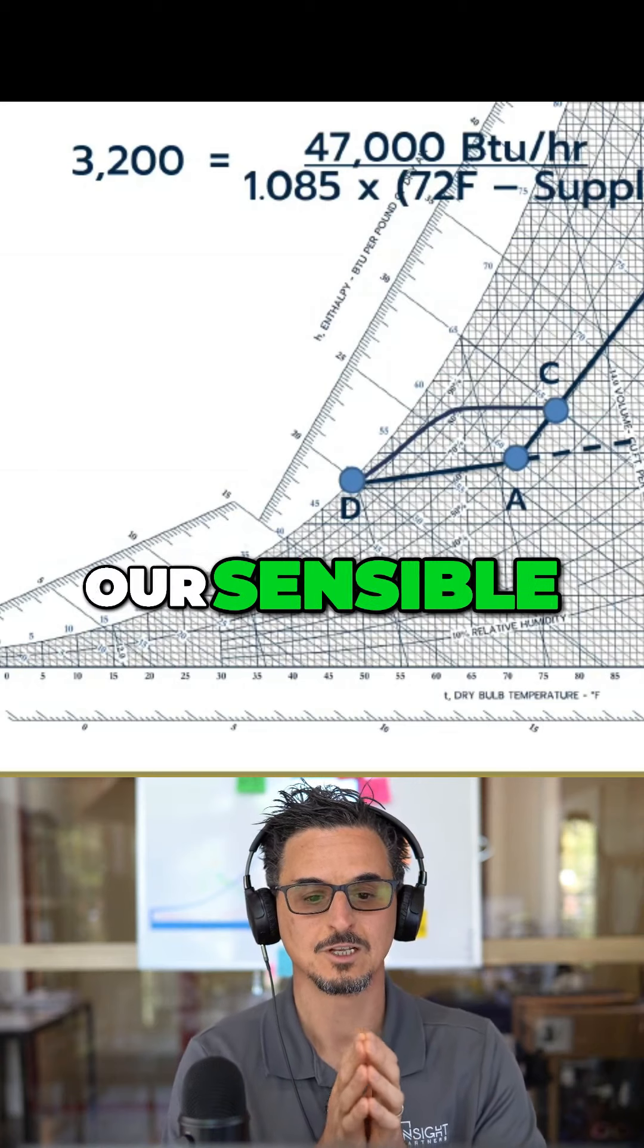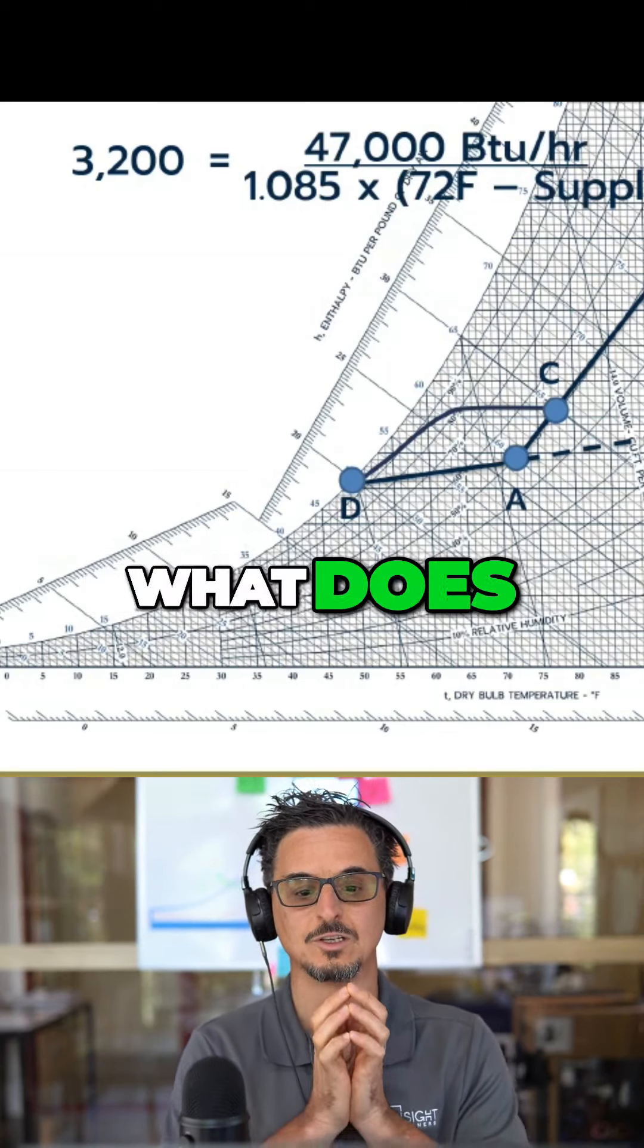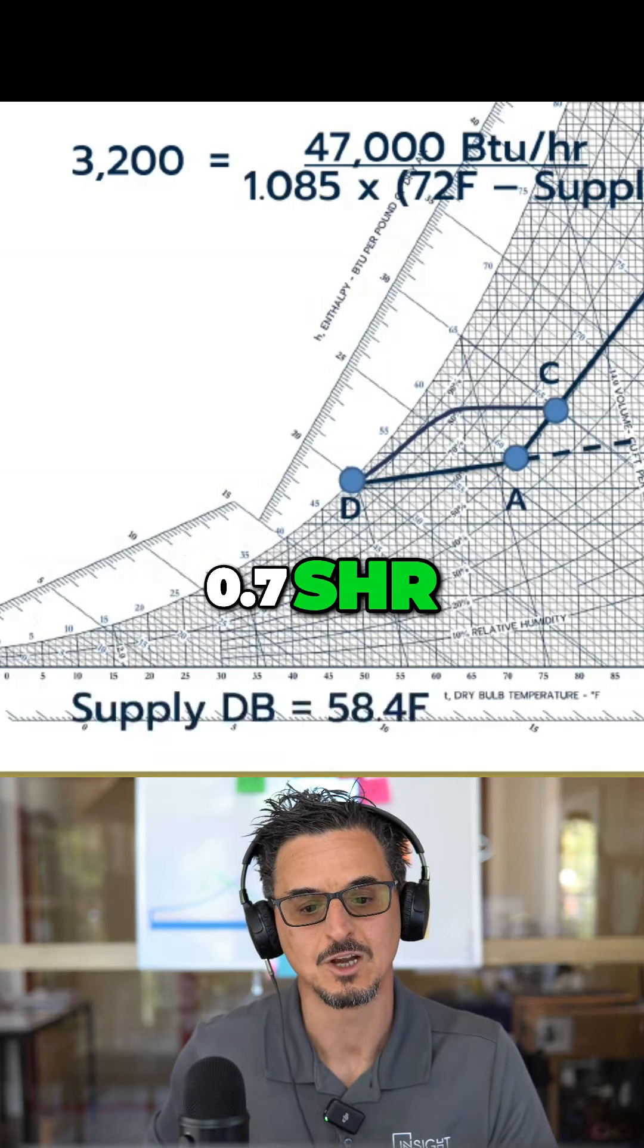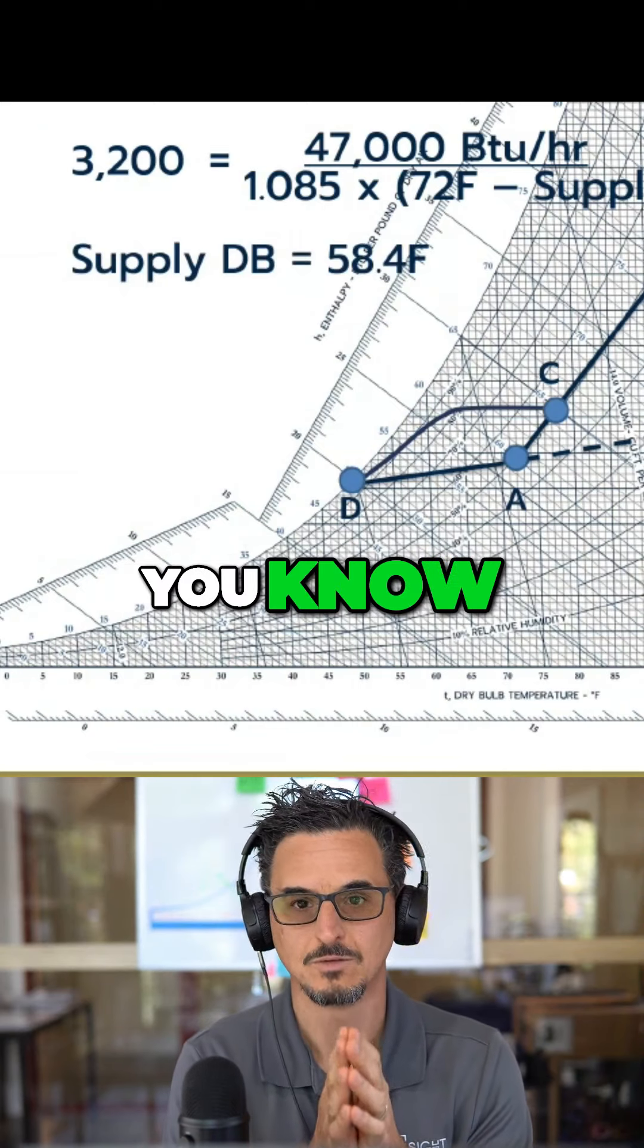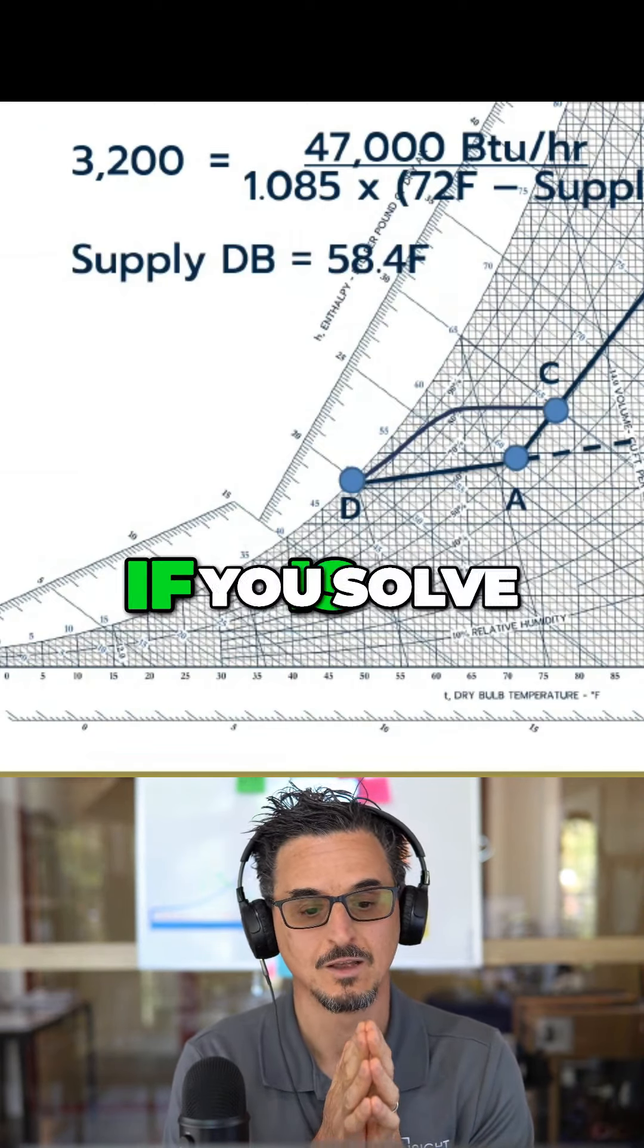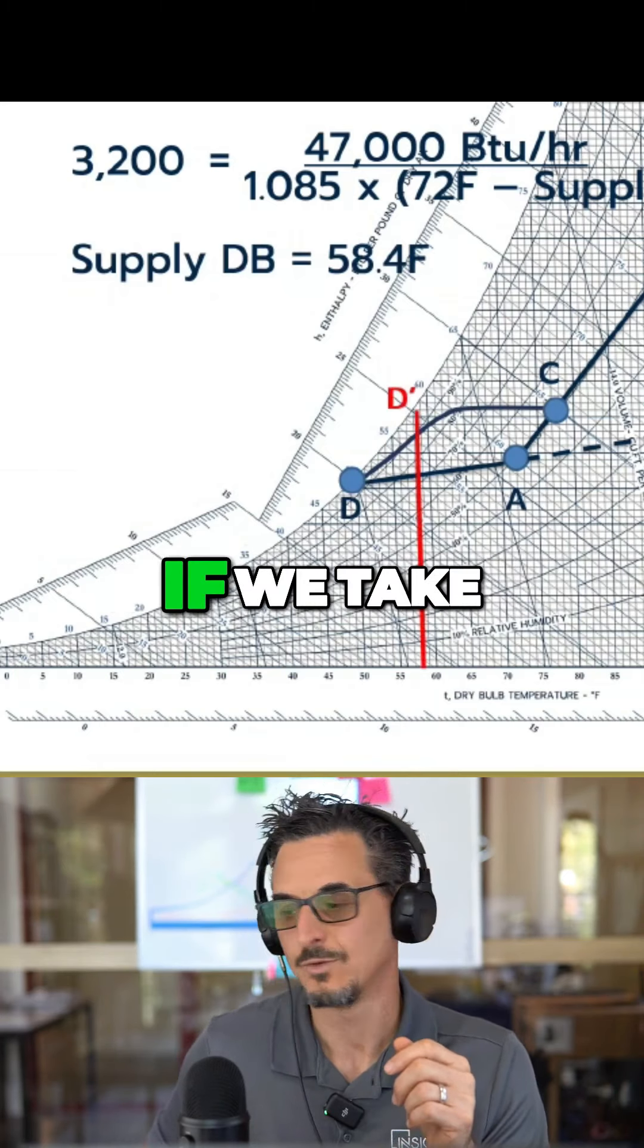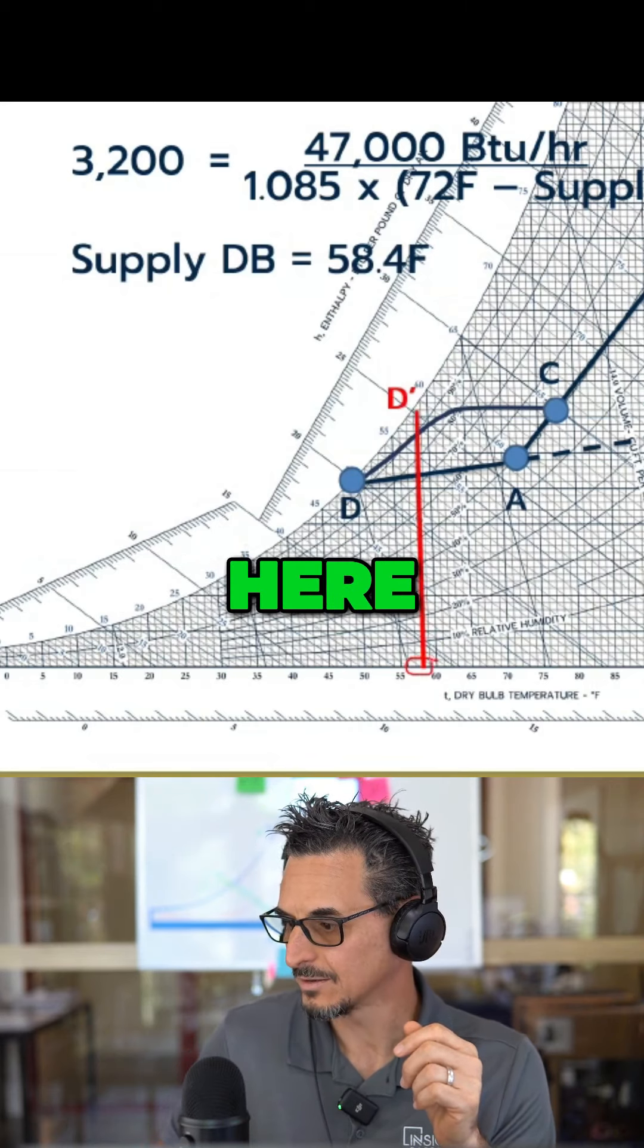There is our sensible heat equation, solving for supply dry bulb. So what does the supply have to be at this 0.7 SHR to not over-cool the space? The supply is, if you solve for this equation, 58.4. Now if we take that and put it in here, we plot it here, 58.4, and we go up to the saturation line, it gets us right here.